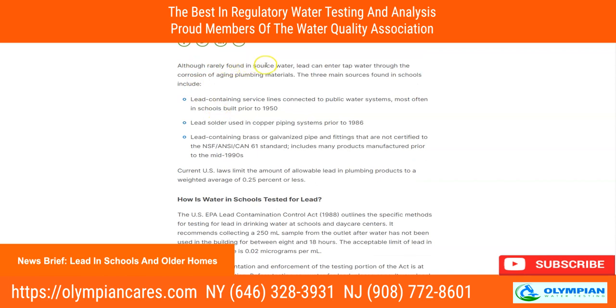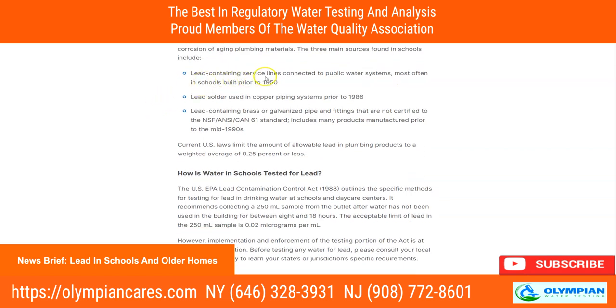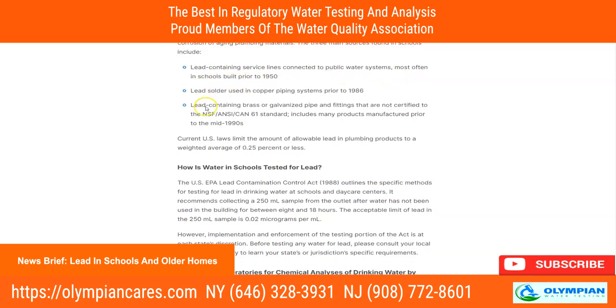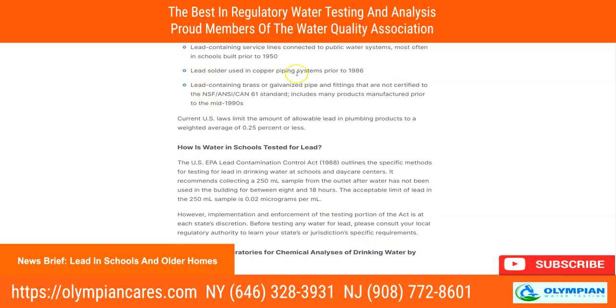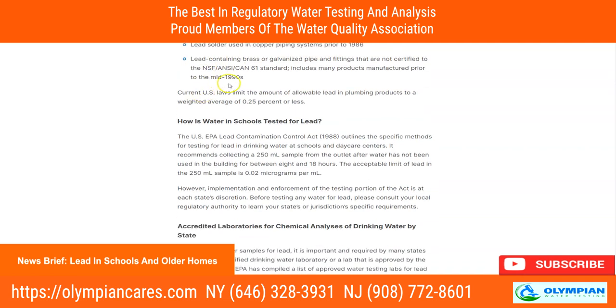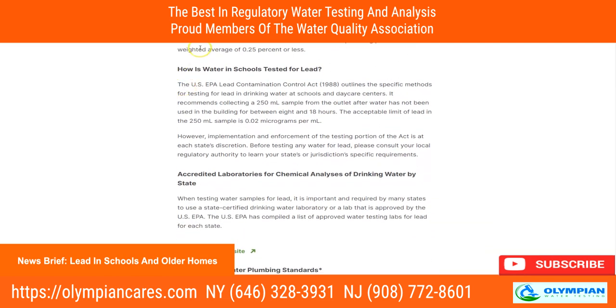Although it's rarely found in source water, lead can enter tap water through the corrosion of aging plumbing materials. Three main sources found in schools include lead-containing service lines connected to public water systems, most often in schools built prior to 1950; lead solder used in copper piping systems prior to 1986; and lead-containing brass or galvanized pipe and fittings that are not certified to NSF/ANSI/CAN 61 standards, including many products manufactured prior to the mid-1990s.